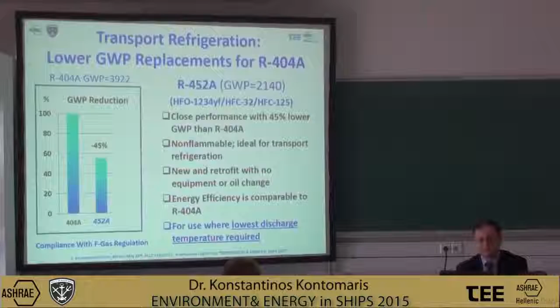this fluid, also registered recently with ASHRAE, R449A, can be used. The advantage of this relative to the previous fluid I was talking about, the 452A, is that it has an even lower GWP, so it moves further in the right direction in reducing the global warming potential. It is also non-flammable and also has the advantage of an easy retrofit. It's a near drop-in, again, replacement of 404A.